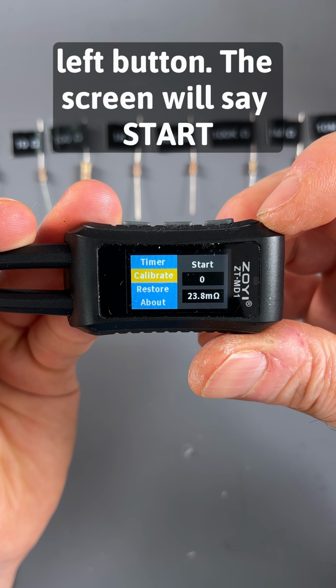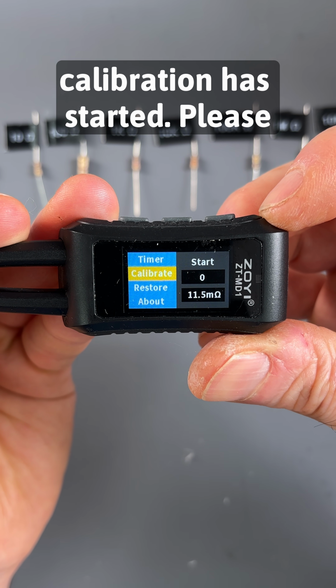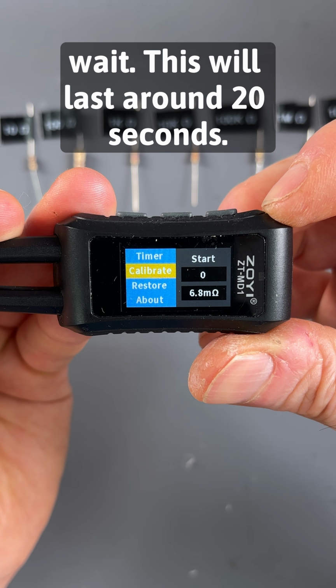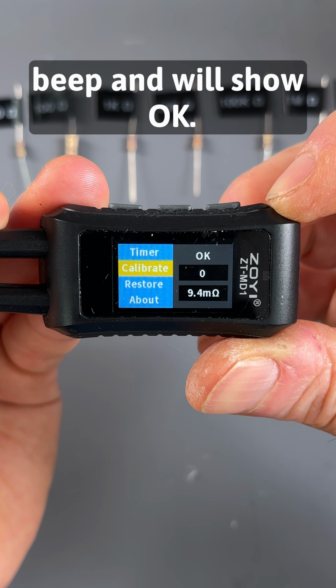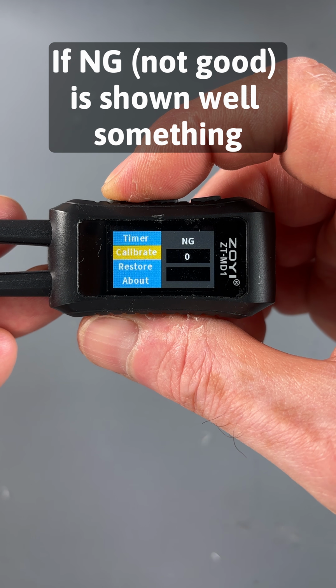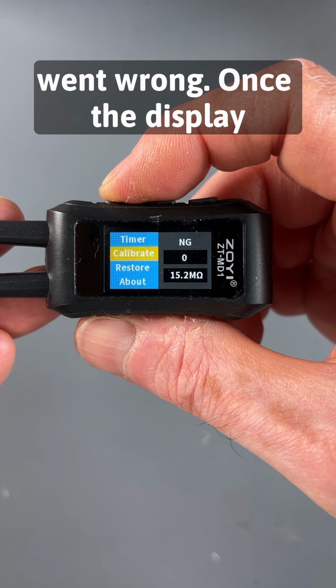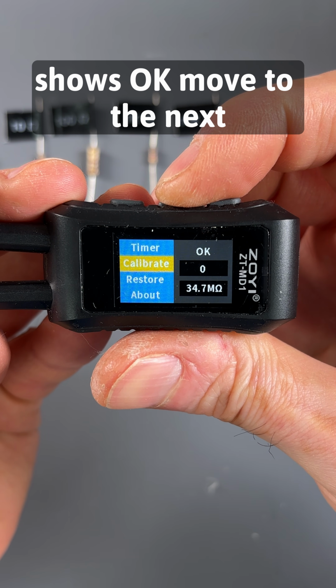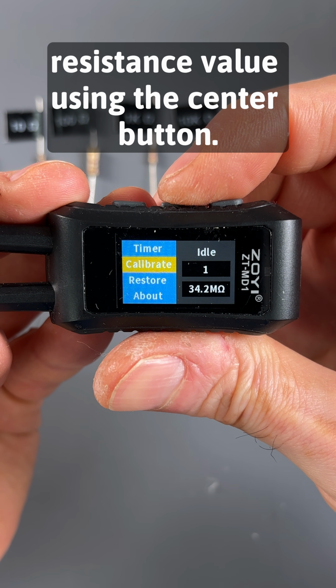The screen will say start, which actually means calibration has started, please wait. This will last around 20 seconds. At the end, the meter will beep and will show OK. If NG, not good, is shown, well, something went wrong. Once the display shows OK, move to the next resistance value using the center button.